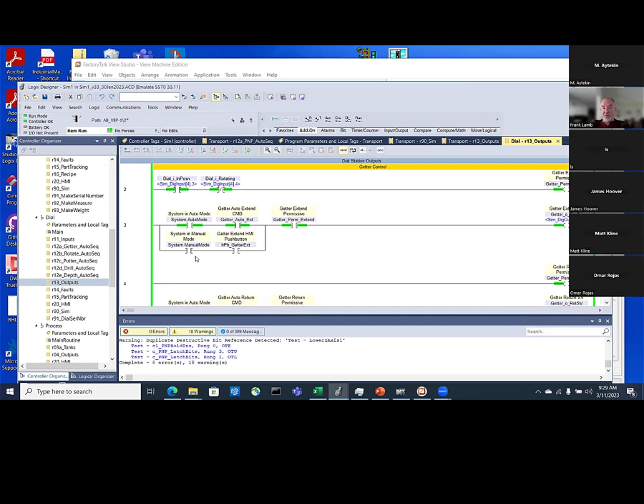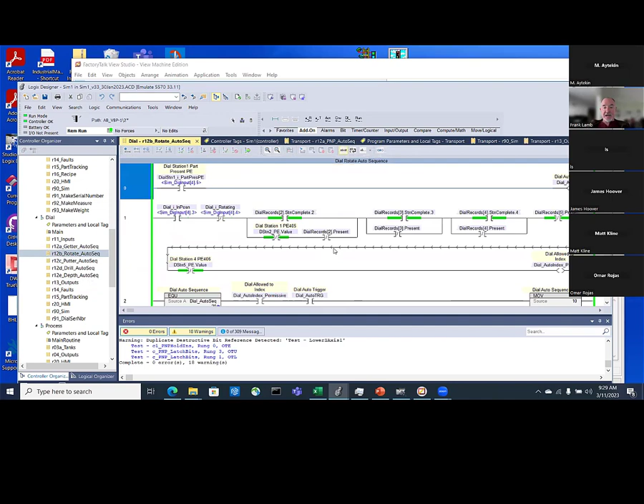And this is where most people start their troubleshooting. They would go here and say, why won't this extend? And I'd go look at the permissive, and that might be the reason that it won't operate. Or it might be, well, it's in auto mode and I'm not in the proper step. And why am I not in the proper step? Because let's see, we'll go to rotate and say, why didn't my dial indexer index? Because some sensor wasn't made, or something wasn't detected to be in position, or this never got to the right physical position.